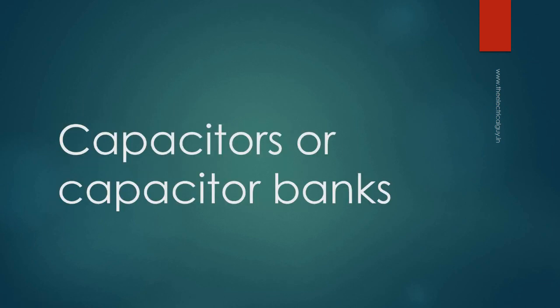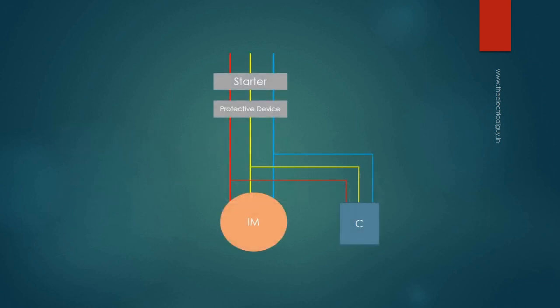Capacitors or capacitor banks are the most commonly used method for power factor correction — you will find them almost everywhere. Most of the time the load is inductive, which draws lagging current and decreases the power factor. For power factor improvement, capacitors are installed in parallel with such loads, providing leading current which neutralizes the lagging component, thus improving the power factor.